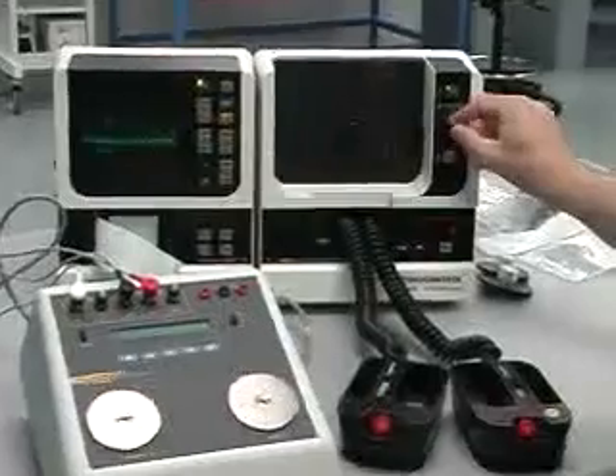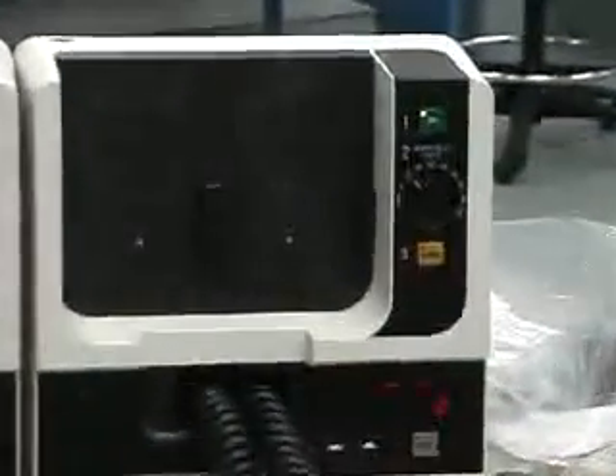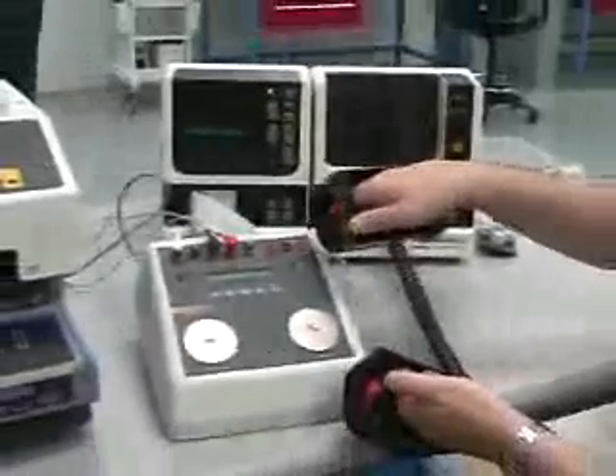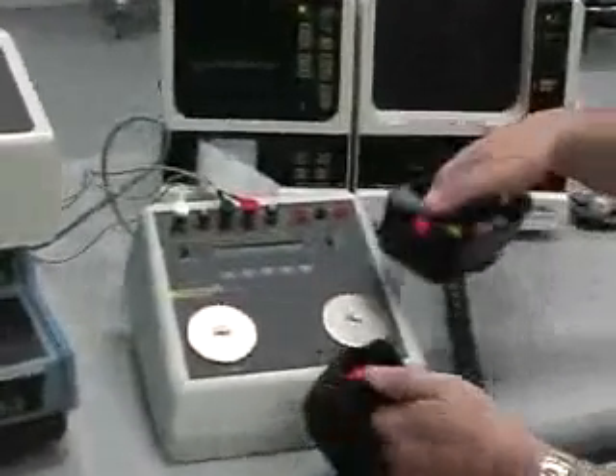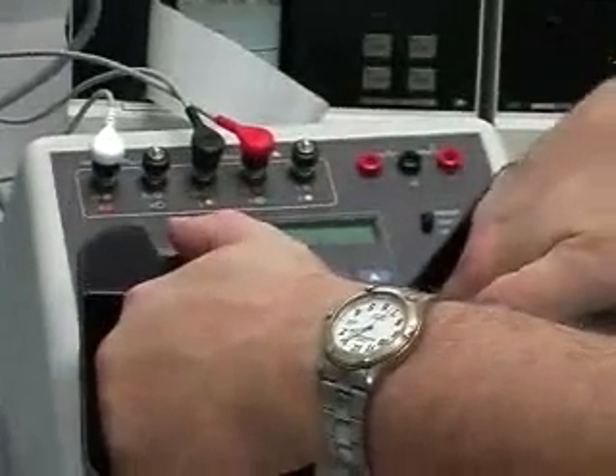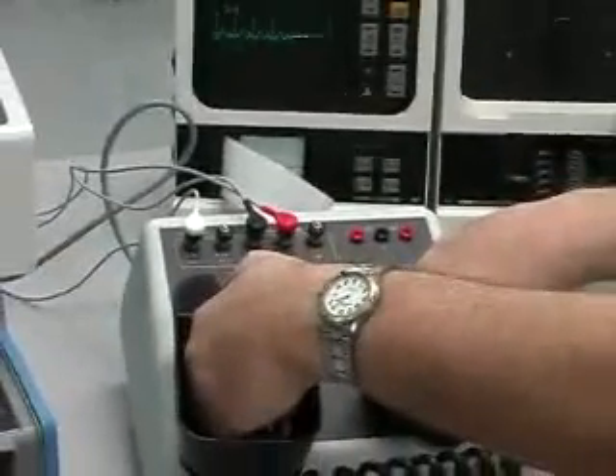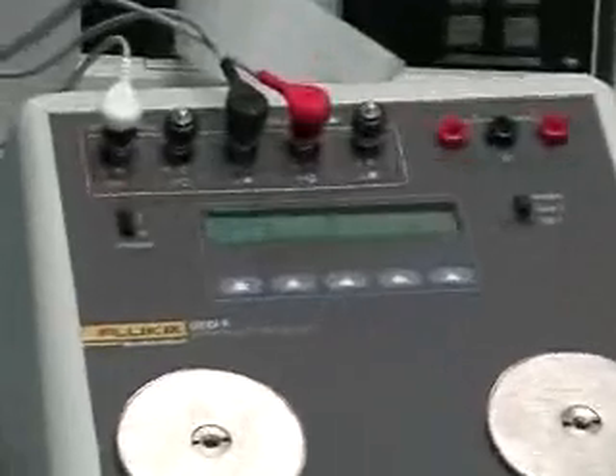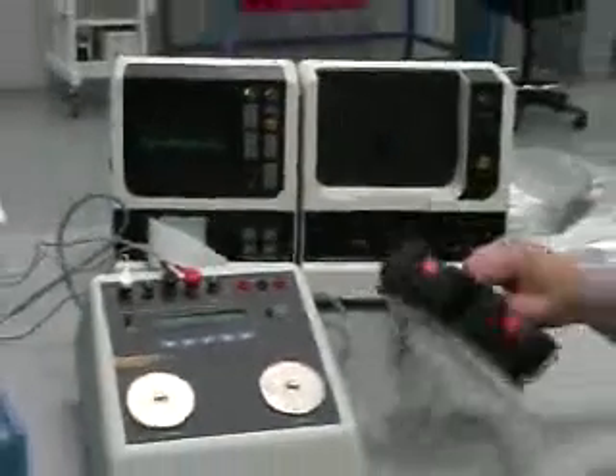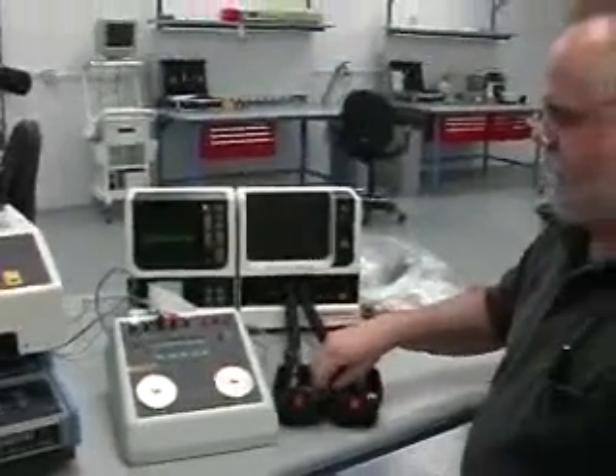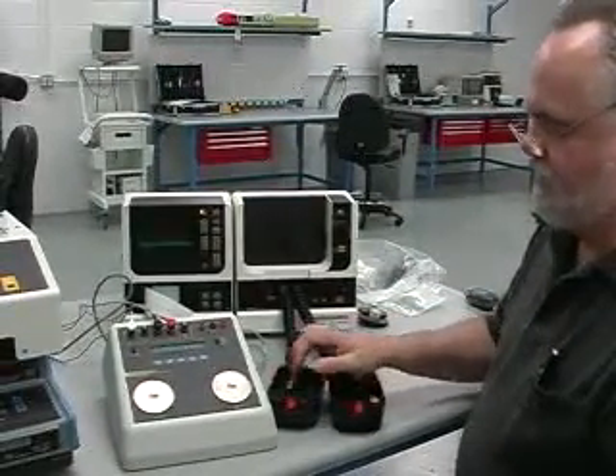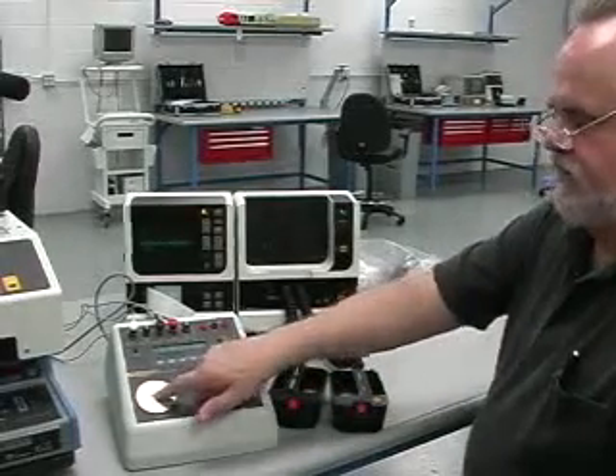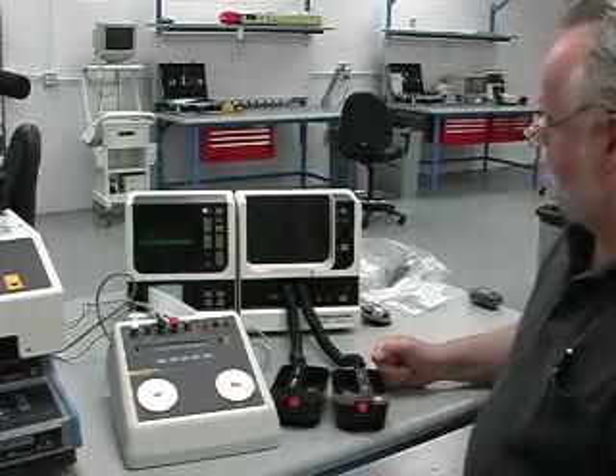For right now, I'm just going to start off at some low energies. Let's go down to 20 joules. This does have the separate charge control on the paddle. Charged up to 20. Get a nice firm connection to the electrodes, and discharge. So we are set at 20 and reading a nice 19.2. So we're in good shape. Okay, this is a more conventional application like we've seen. These are the older mechanical paddles. The analyzer is also compatible where you can plug in adapters for the different disposable electrode sets too.